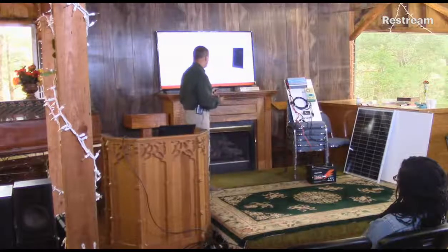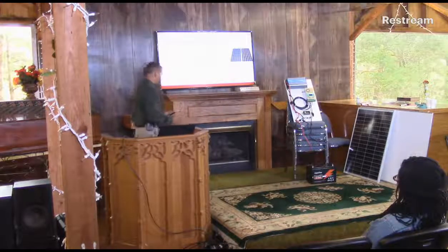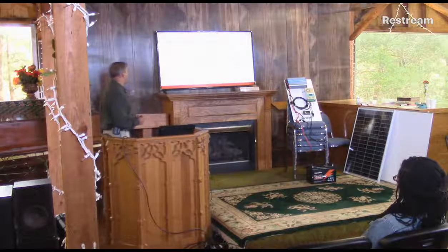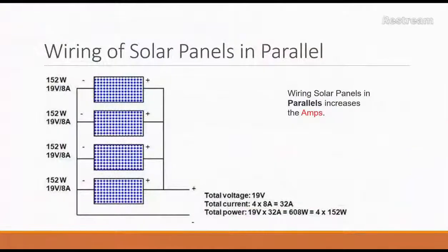The other part is wiring in parallel. So this basically takes you through what each panel has - the watts, the volts, and the amps. Like I said, when you wire in parallel, you're increasing the amps. So if you look at that, there's 8 amps per panel, and you times that by 4, you get 32 amps. So you're able to get more charge into the batteries quicker.